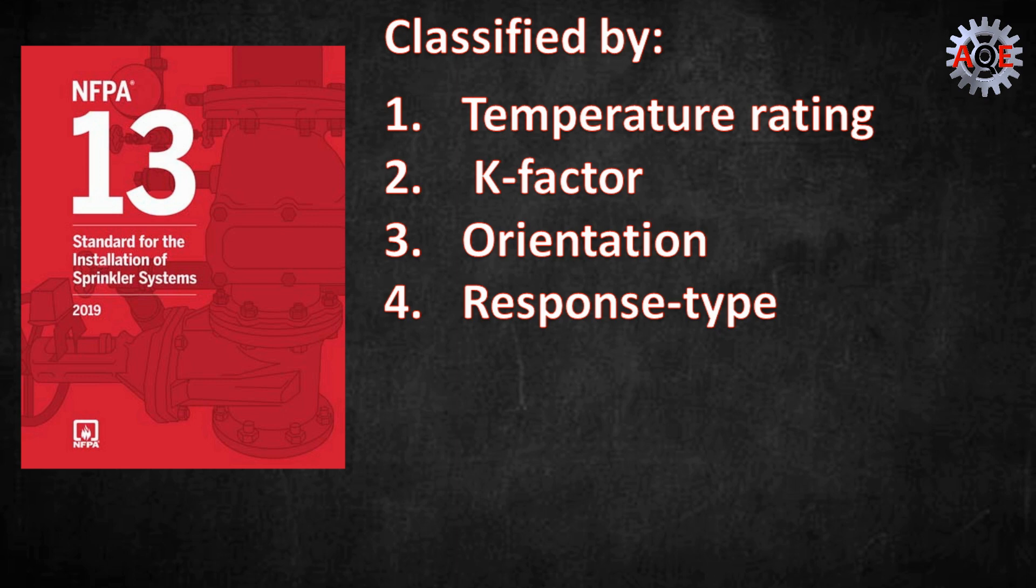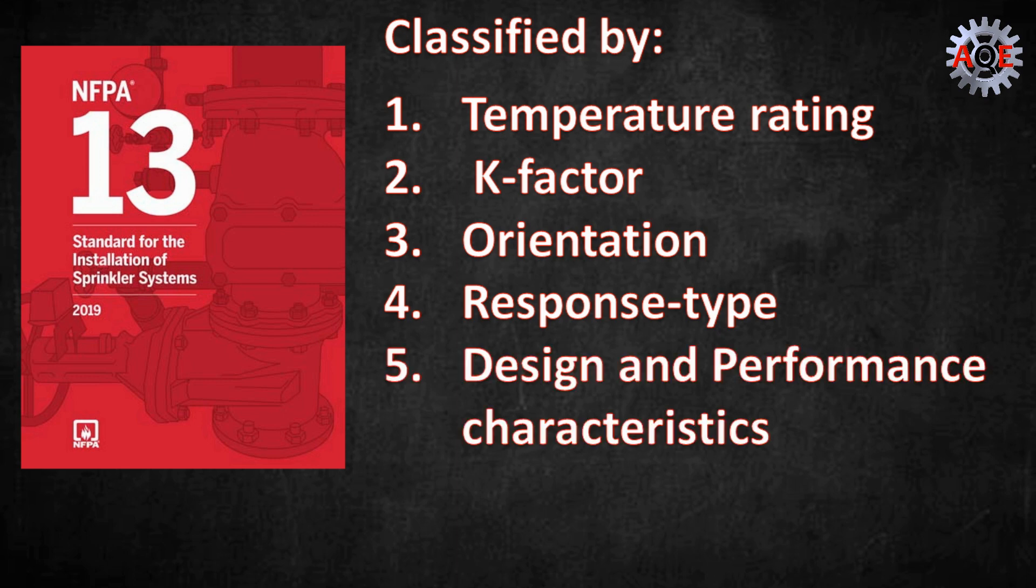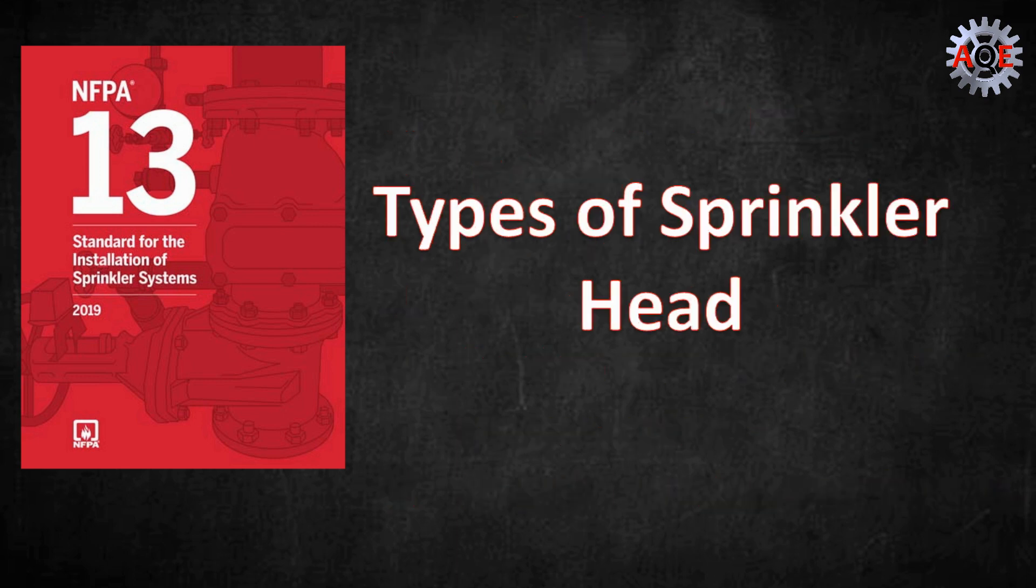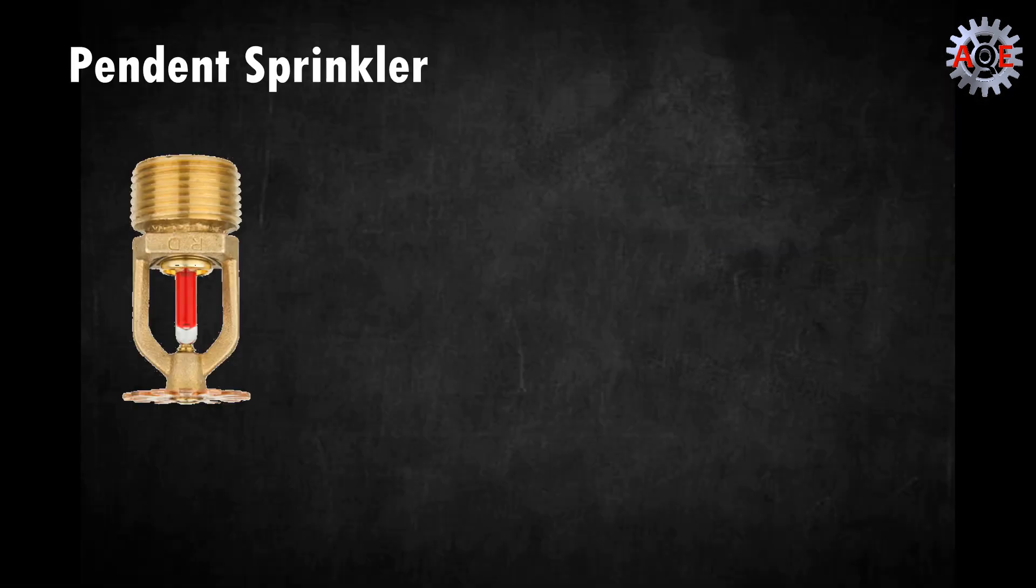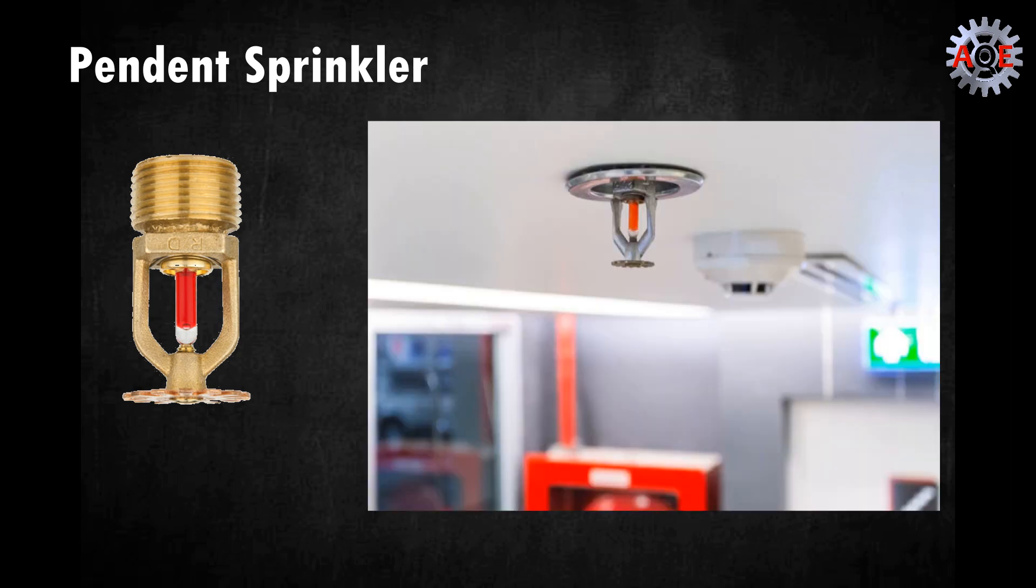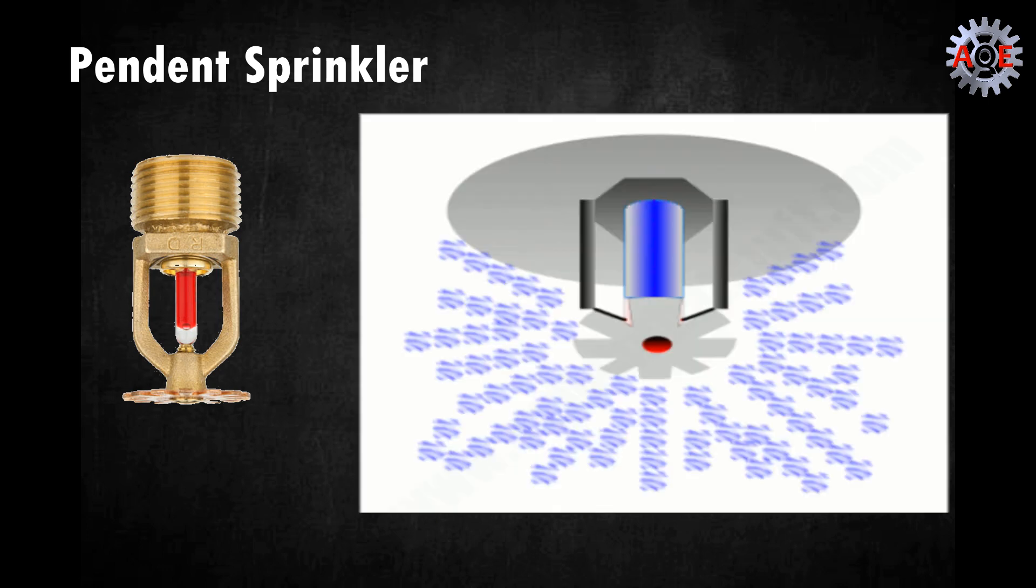There are four primary types of sprinkler heads for fire protection. Each one is specifically designed to extinguish fires and they come in a variety of temperatures, finishes, and sizes. The pendant fire sprinkler head is the most common type and it's mainly used in offices, hotels, and factories. It hangs down from the ceiling and sprays water in a circular motion to cover the most ground. The deflector, the metal piece at the end, is curved down in order to direct the water in a cone-shaped position.